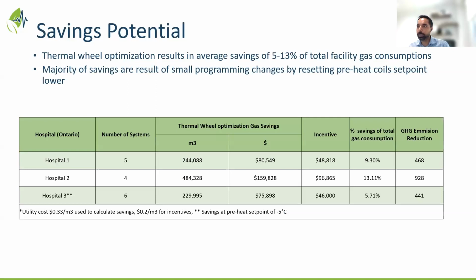Just quickly, the savings potential. What we are generally seeing is between 5 to 13% across the facilities. The 5% you see here is slightly lower because the calculations were done at a pre-heat setpoint of -5, because of the limitation of the existing infrastructure of the facility. But overall, there's a huge incentive in achieving those savings, and it brings down your overall facility consumption by 5 to 13%. Our rough number is around 10 to 15% that you will achieve if you have thermal wheels in your facility and optimize them to the recommendations of resetting those pre-heat setpoints. It's also done through minor programming changes in most of the facilities and doesn't need a lot of capital work.